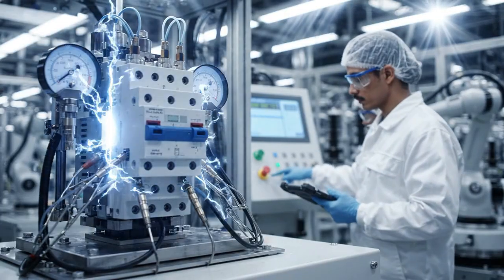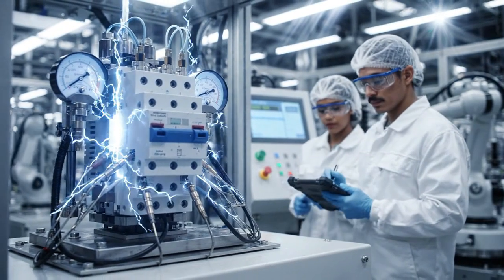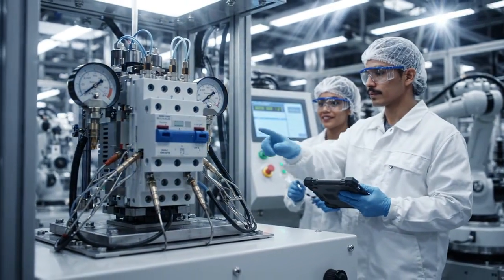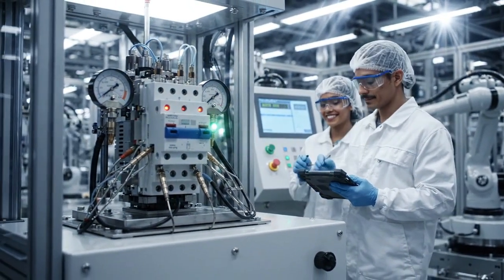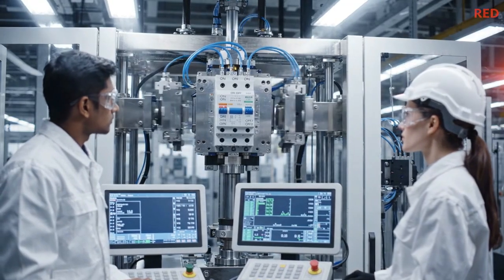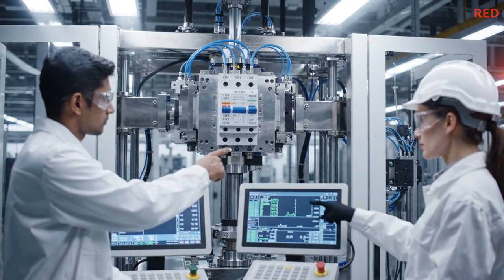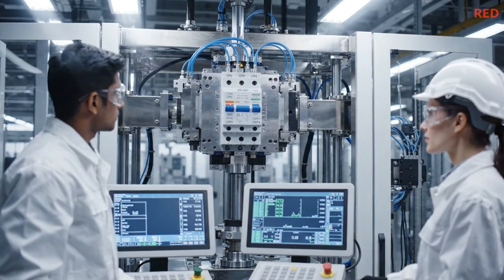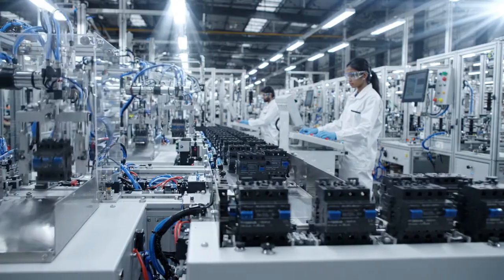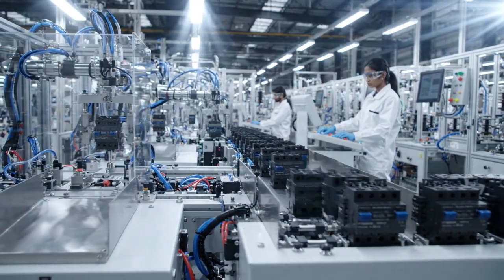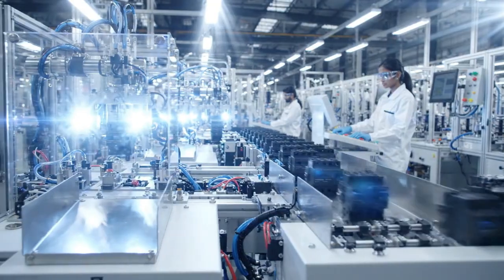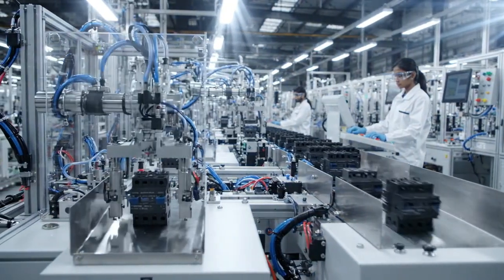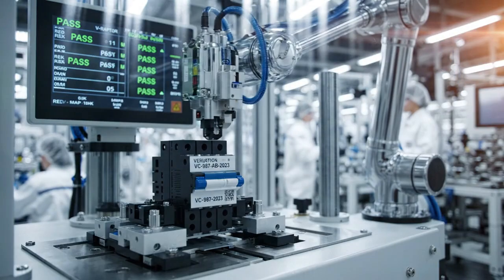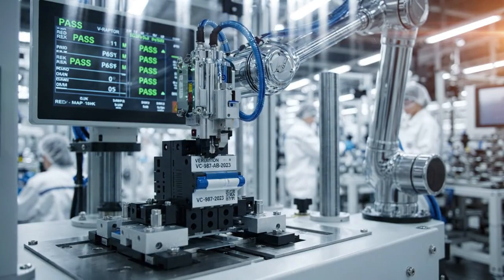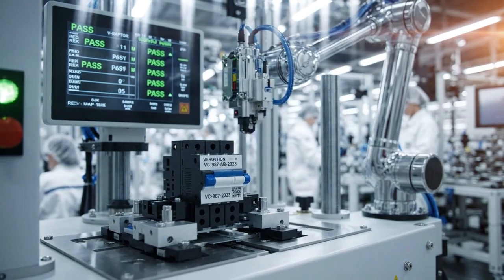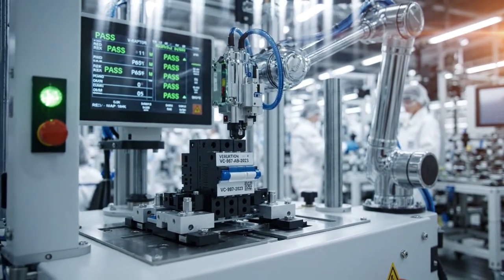Dielectric testing proves the breaker's insulation integrity. Voltage twice the rated level plus 1000 volts is applied for 1 full minute without breakdown. Endurance testing cycles the breaker thousands of times at rated current, simulating years of normal switching operation to verify mechanical reliability. Every test result is electronically recorded and linked to the breaker's serial number, providing lifetime traceability of manufacturing quality.